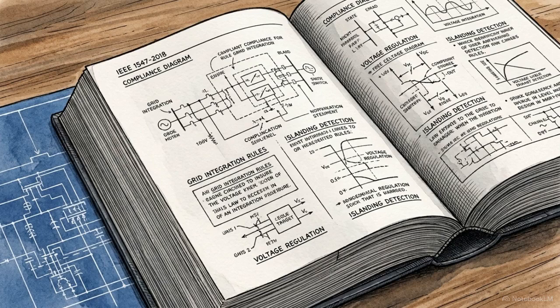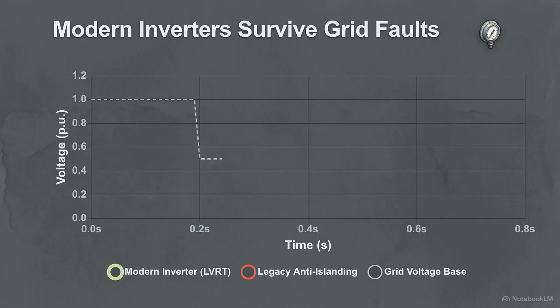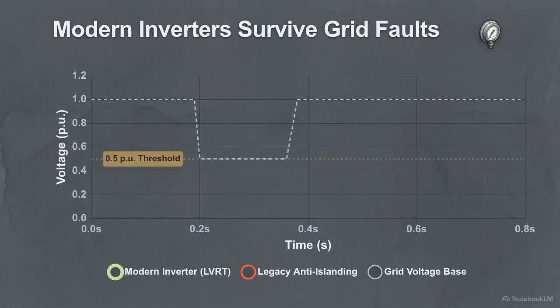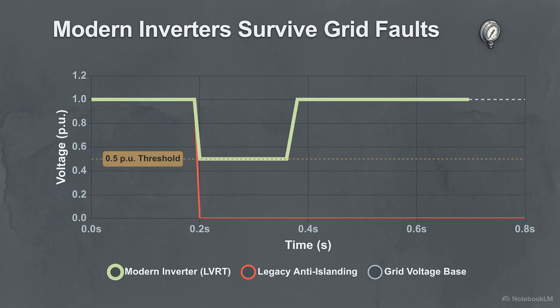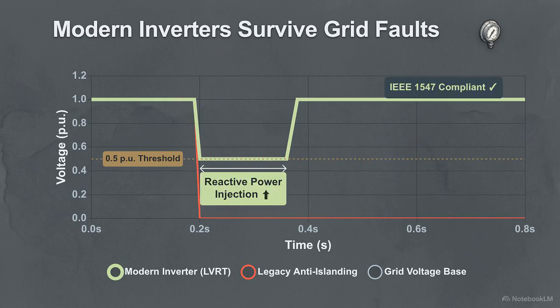Now, distributed energy resources are legally mandated to actively support the macrogrid during an anomaly. This chart shows the required mechanism, the low-voltage ride-through curve. While older hardware would instantly shut down during a voltage drop, modern inverters track this curve and remain connected. They inject reactive power to pull the macrogrid's voltage back up.